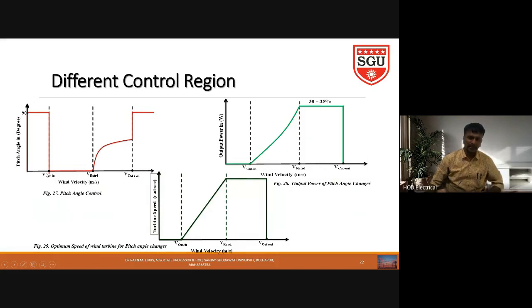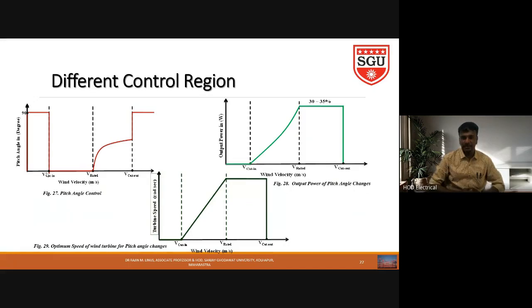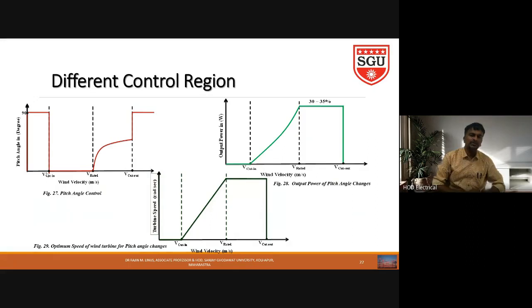In some ideal cases, when wind velocity is below V_cut-in, the machine may actually draw power from the grid, which is a loss for the wind farm and the power system. To avoid this, we will not allow wind to hit the turbine blades — we make the pitch angle equal to 90 degrees. So in the region from 0 to V_cut-in, the pitch angle is set to 90 degrees.